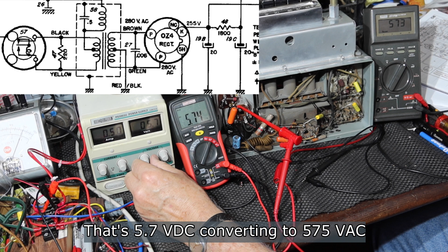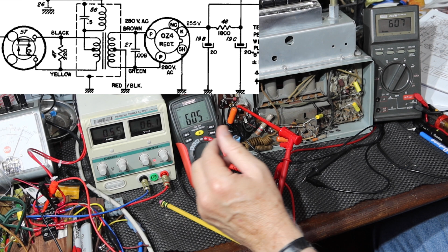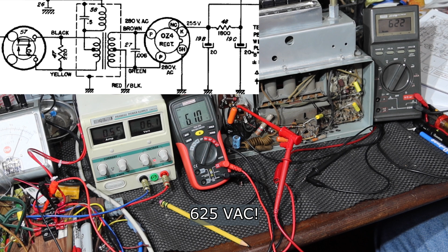It behaves like a capacitor's charge is forming, doesn't it? There we go, 6 volts, 0.55 amps, 625 volts AC out of the transformer. We got a good transformer. But I'm going to let it run for just a bit, and I'm going to check to see if the transformer's hot. Then if everything seems reasonably okay, I'll bring you back and we'll talk about putting the rectifier in and see how we get there.